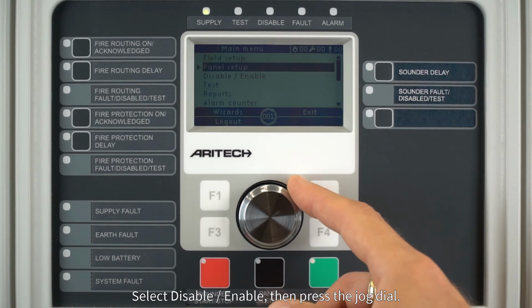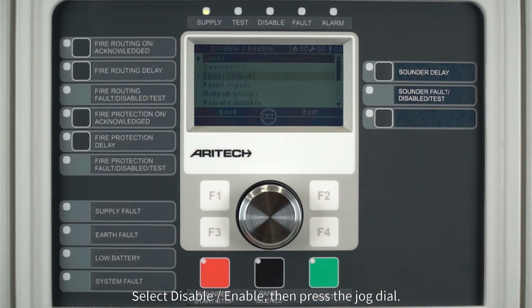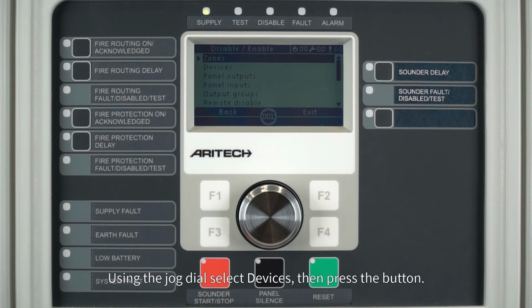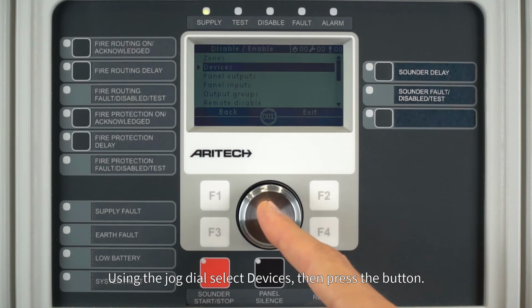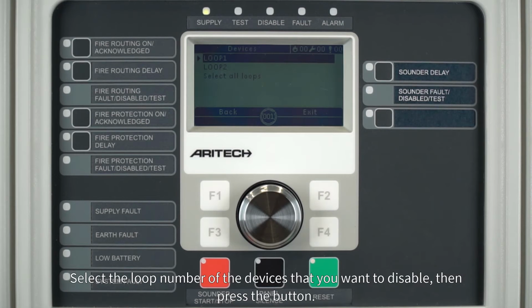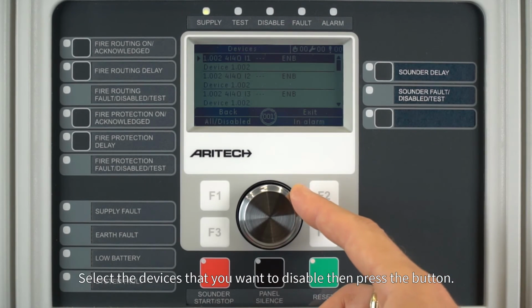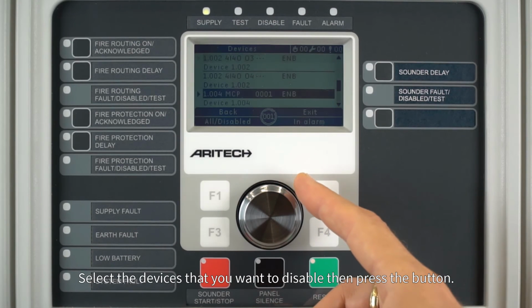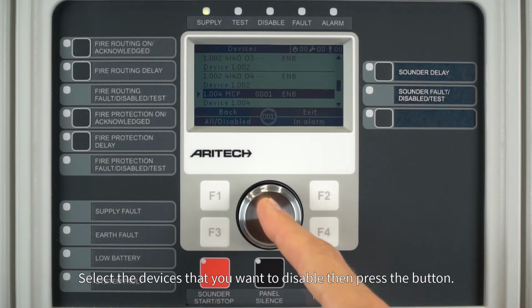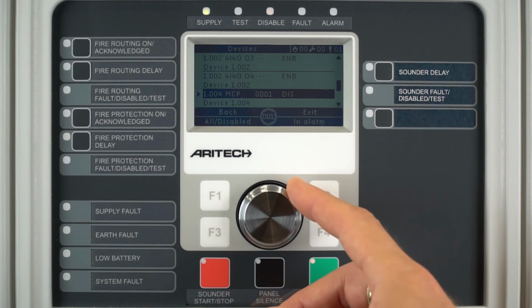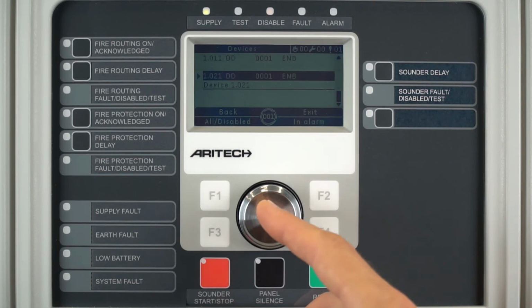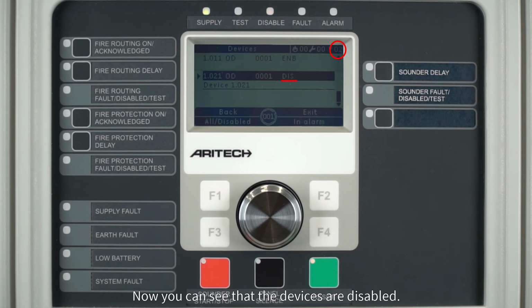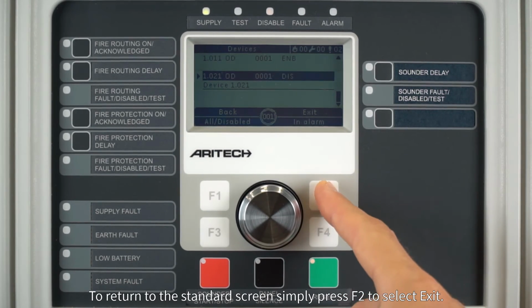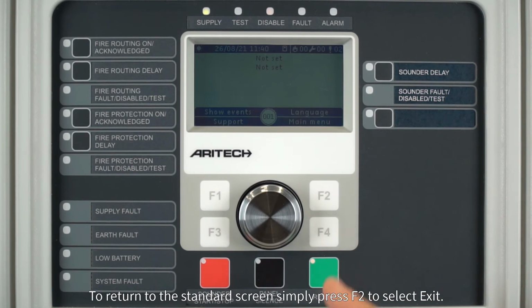Select Disable Enable, then press the jog dial. Using the jog dial, select devices, then press the button. Select the loop number of the devices that you want to disable, then press the button. Select the devices that you want to disable, then press the button. Now you can see that the devices are disabled. To return to the standard screen, simply press F2 to select Exit.